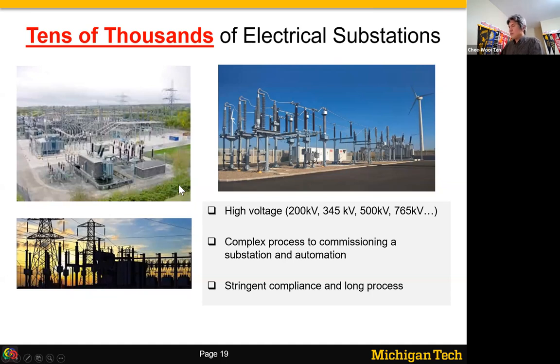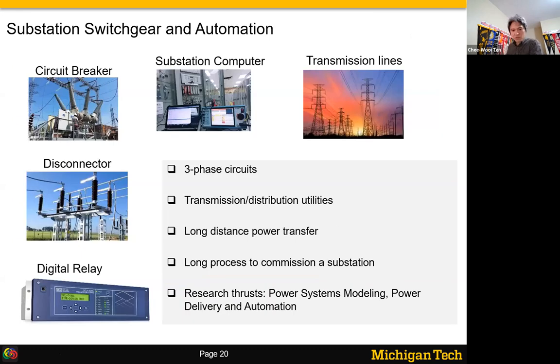These days, because of communication technology, we are shifting this to more IP-based systems. What you see here is the substation automation framework, where everything has changed from electromechanical relays to the digital world. The digital shift is for interoperability between different vendors. Each substation has at least a few dozen of these boxes called digital relays that send signals to the circuit breaker whenever there's a short circuit current, so the breaker can do its job in a split second.